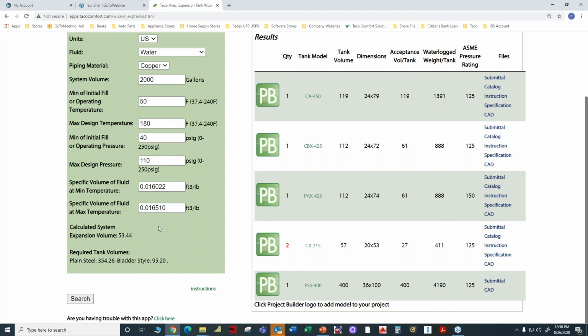Well, depending on the system, I was just reviewing a geothermal system a little bit earlier today. A plastic will actually expand a little bit more than copper. And depending on how much plastic there is in the system, some engineers will actually design a geothermal system using plastic pipe and not install an expansion tank because the plastic will expand enough to accept the volume of expansion of the fluid as the temperature increases. But I always recommend, whether using plastic or steel or copper or some other material, to utilize an expansion tank.